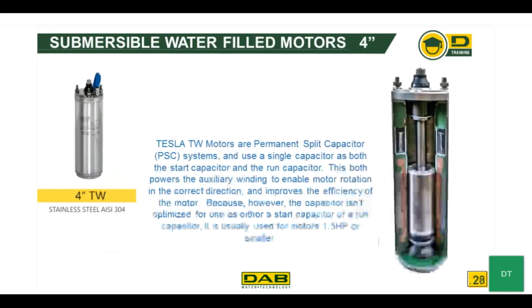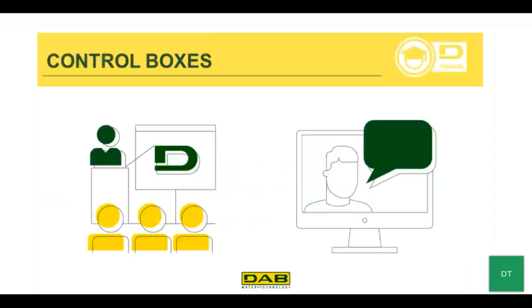We have the 4-inch TW motor. The Tesla TW motors are permanent split capacitor systems and use a single capacitor as both the start capacitor and the run capacitor. This capacitor is located inside the motor, so a control box is not necessary. This capacitor powers both the auxiliary winding to enable motor rotation in the correct direction, and it improves the efficiency of the motor.